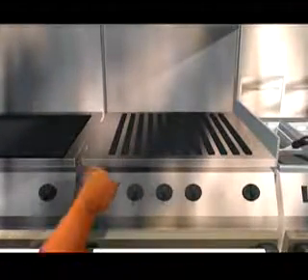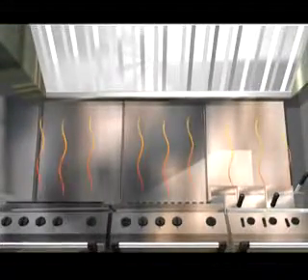Using highly sensitive heat transponders located inside the hood, Novio's patented Centris module ensures real-time temperature fluctuation monitoring over the cooking area. Through what is known as a handshake protocol, the Centris module varies the exhaust hood motor speed to reflect real-time demand based on the intensity of cooking operations.